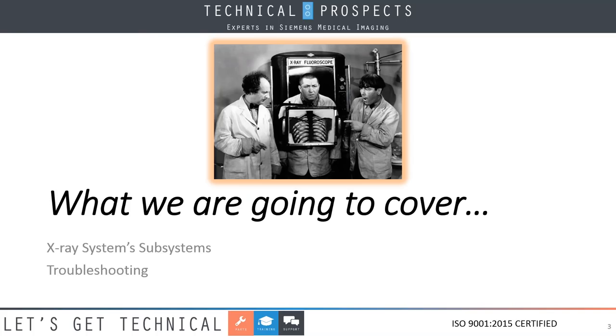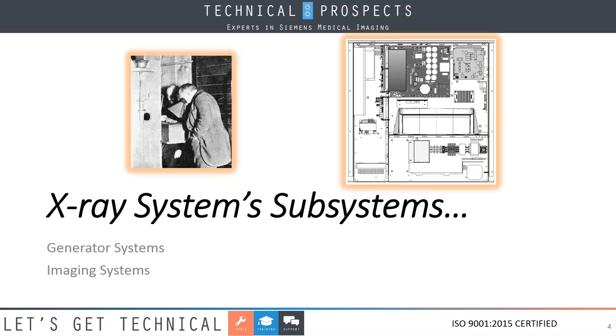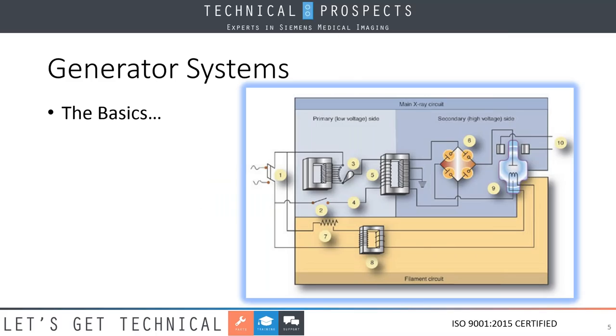We're going to talk about X-ray systems, subsystems, and then lastly, what you're all here for, troubleshooting. So let's jump right into our X-ray system subsystems. Here we're going to take a look at both the generators and also the imaging systems themselves. Starting with the generator systems, I've got a little diagram here of what the basics are all about. But when we look at an X-ray system, typically there are 5 basic systems that are incorporated in every X-ray machine.